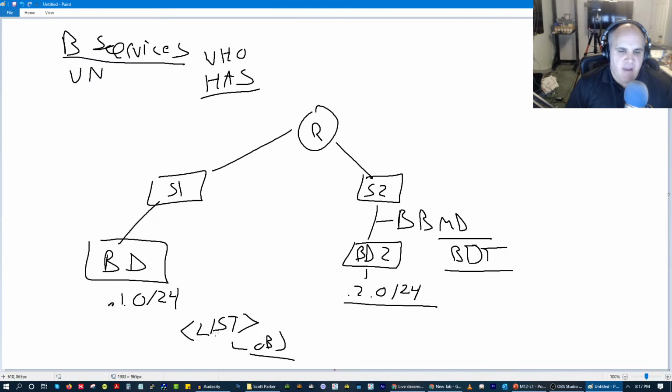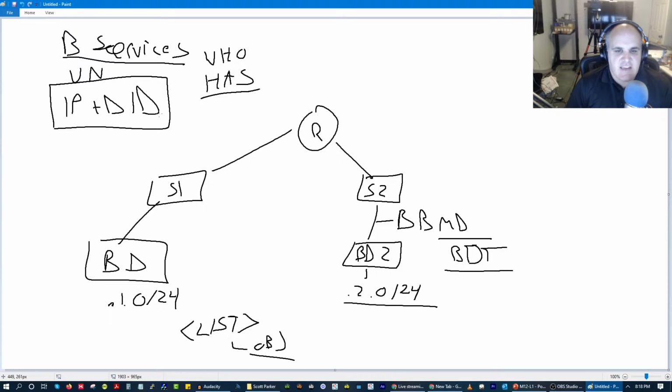Once we build out this BACnet list and this object list, unless anything's changed, we're going to be using unicasts and multicasts for our read property multiple, write property multiple. And remember, unicast messages are going to go to the BACnet device, the BACnet address, which is simply the IP address plus the device ID. Now, the important point to know here is this IP address and device ID, since it's a unicast, will simply use the route that is in the routing table.